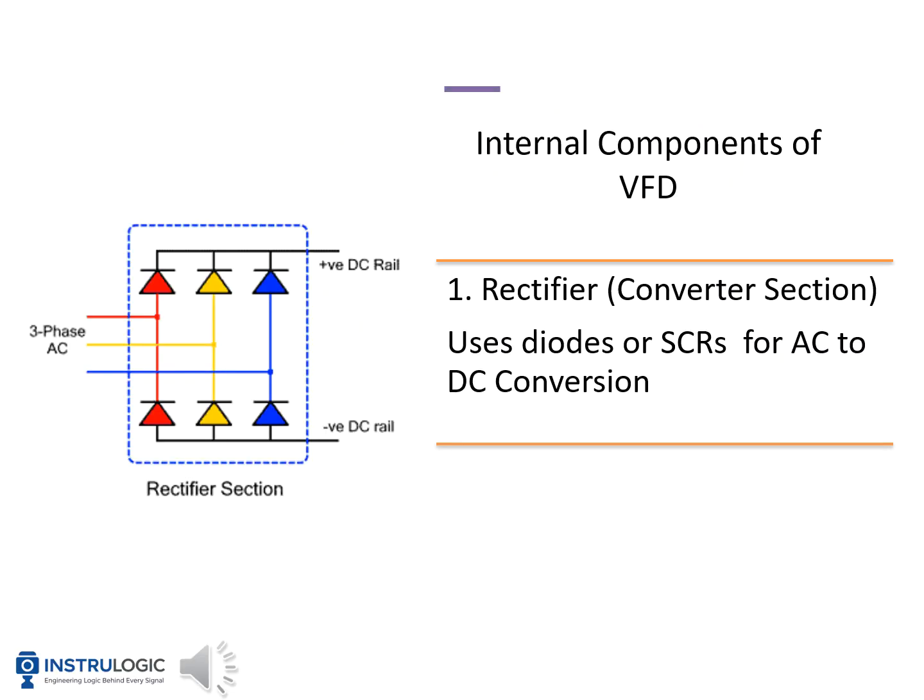Let's look at the first internal component of a VFD, which is the rectifier section, also called the converter section. The rectifier converts AC power into DC power — this is the first step in the VFD process. It uses diodes, or sometimes SCRs (silicon-controlled rectifiers), to achieve this conversion. Diodes allow current to flow in one direction, converting alternating current into direct current. SCRs are used for controlled rectification in more advanced applications. The three-phase AC input enters the rectifier, and the output is a DC voltage across the positive and negative DC rails, which then moves to the DC link or filter.